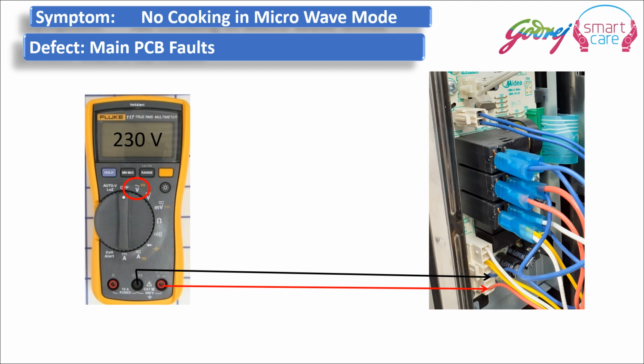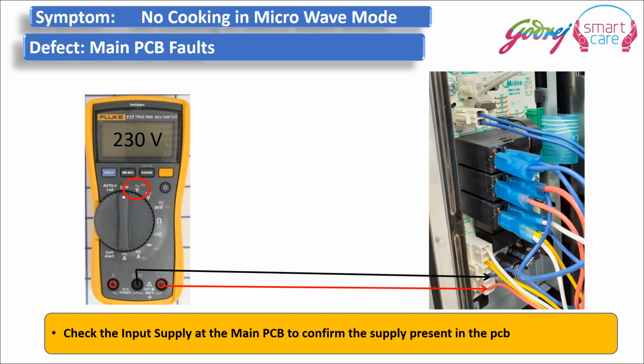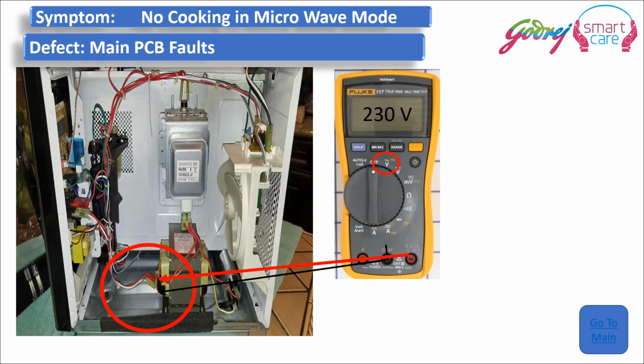We can check the input to the PCB, the red and the blue wires which are shown on this white connector. Across these two wires we should get 230 volts. This is the input to the main PCB. Then from the main PCB to the primary side of the HV transformer, as shown in this picture, we have to check whether the 230 volt supply is coming from the main PCB to the HV transformer when we are selecting the microwave mode.